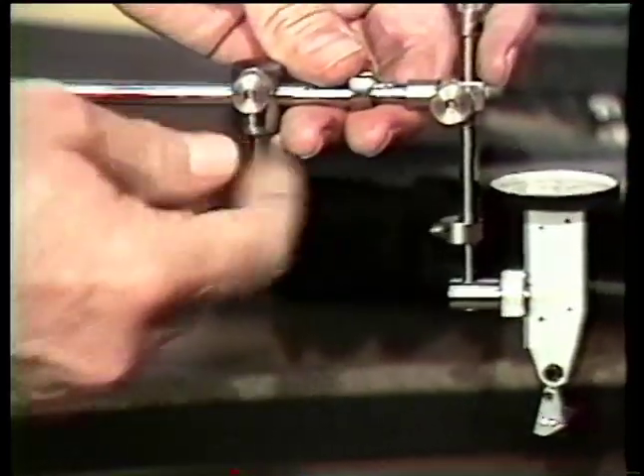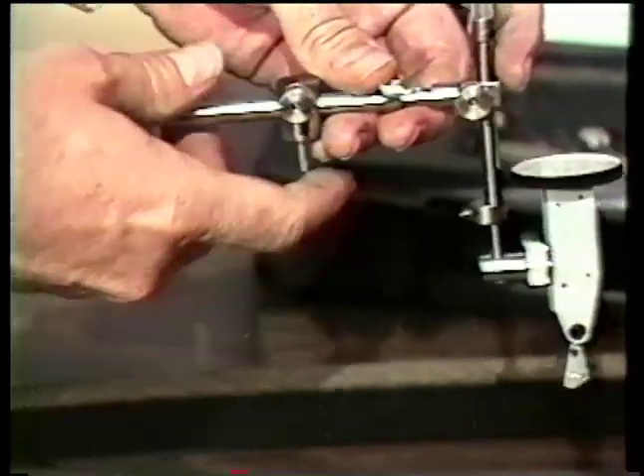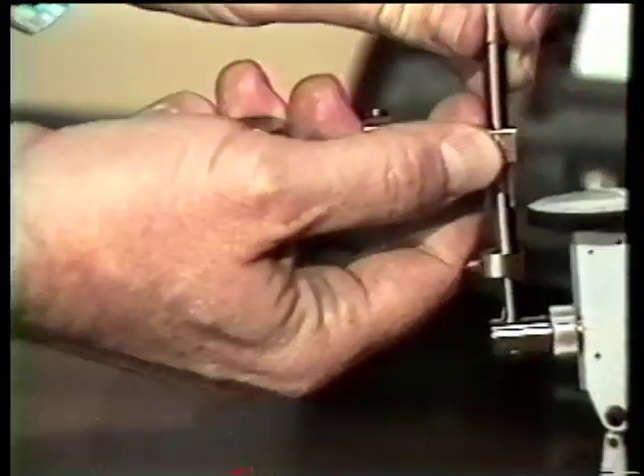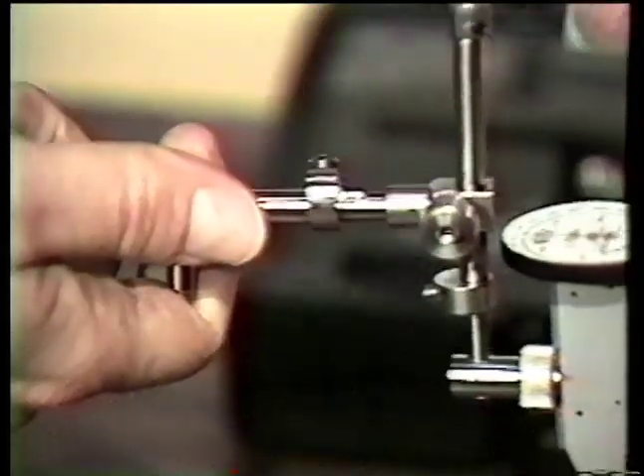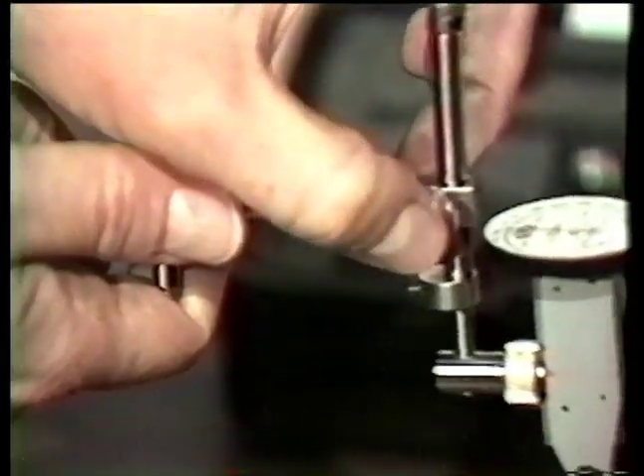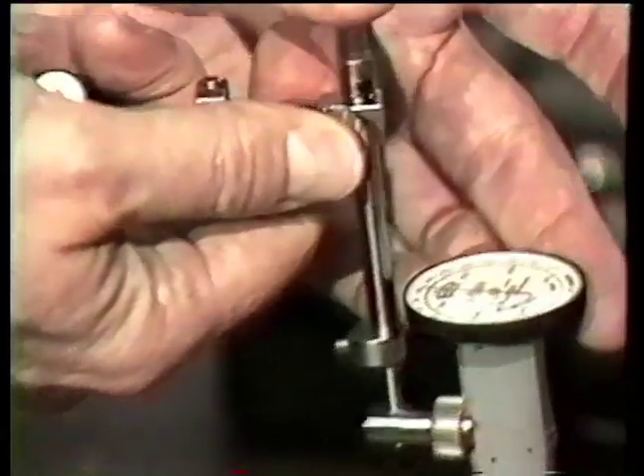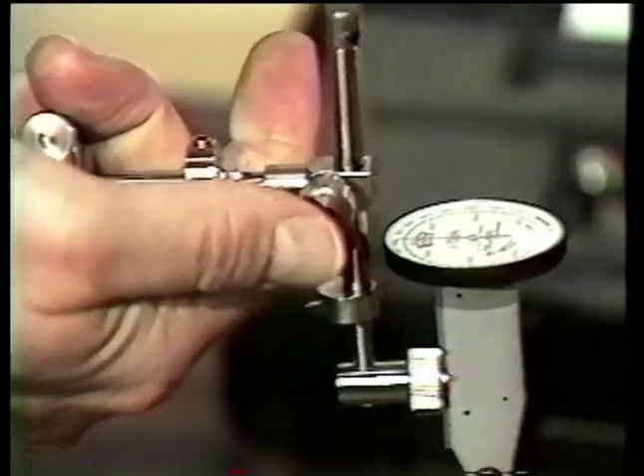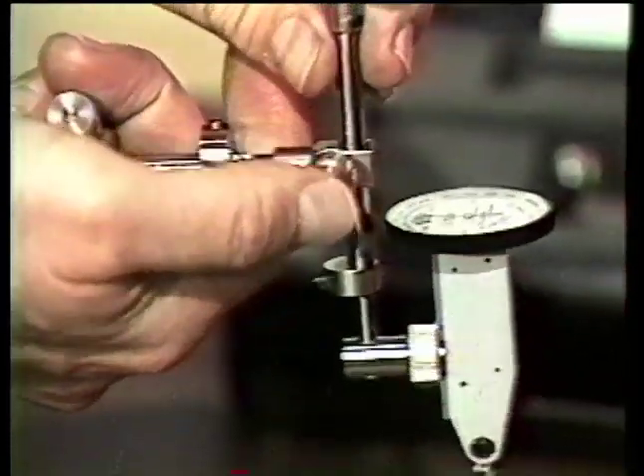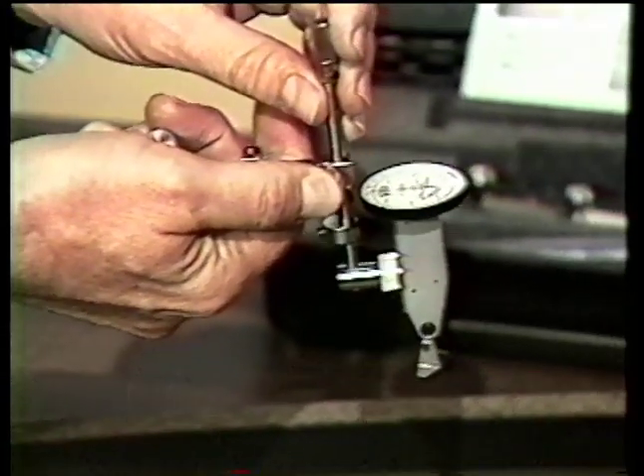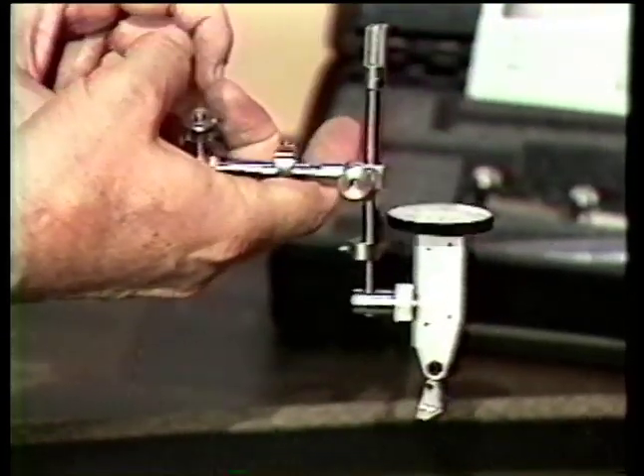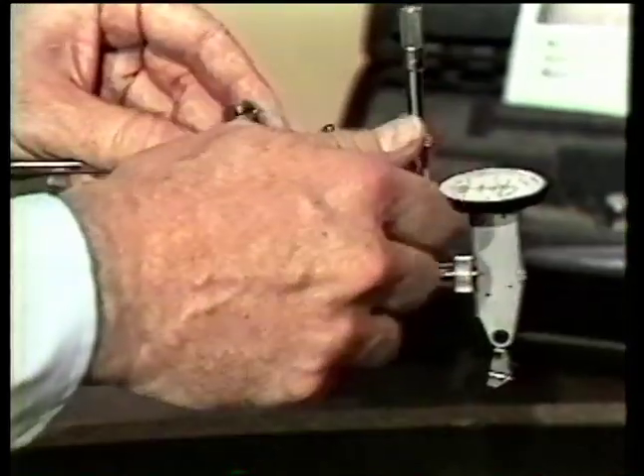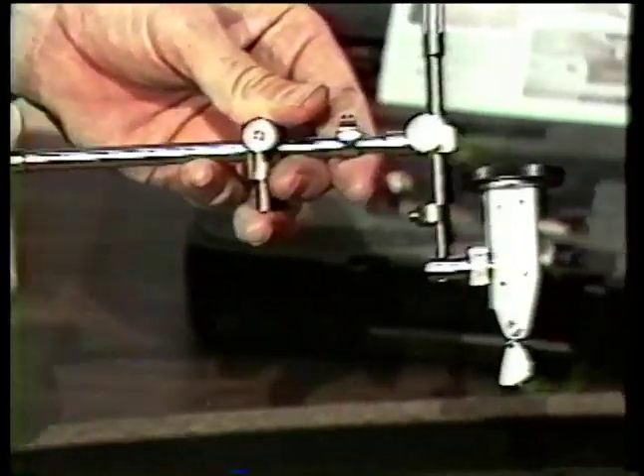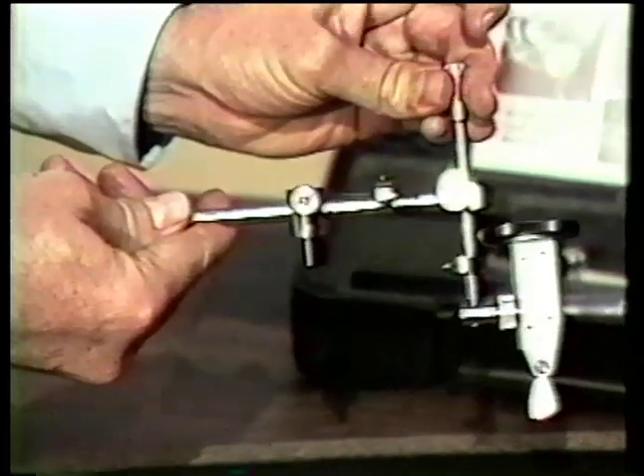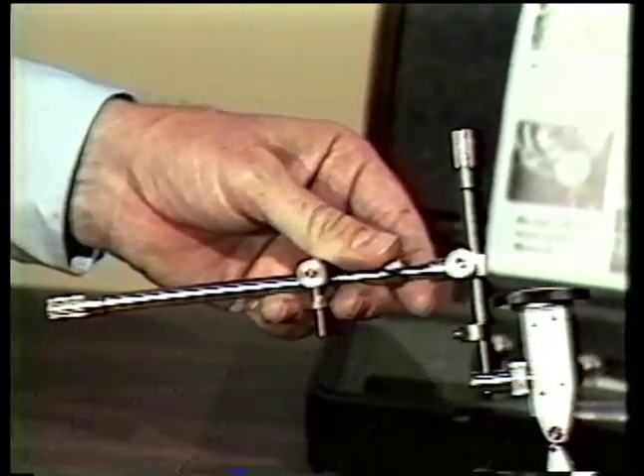It should be pointed out at this time that each of these knobs is actually spring-loaded. We did that on purpose so that the gauge wouldn't drop into the machine accidentally unless you push the button. And of course you can see that would not be a good situation. So when you're adjusting it, just push the button and then you can do the coarse adjustment this way. But when you let go, there's enough force to hold the indicator from moving. Once the coarse adjustments have been made, there are micrometer adjustments for both the horizontal as well as the vertical to do the final positioning of the tip against the little drum.